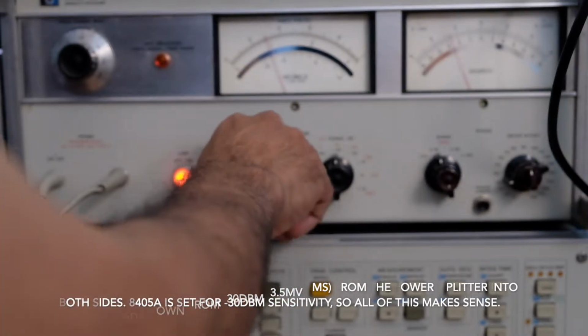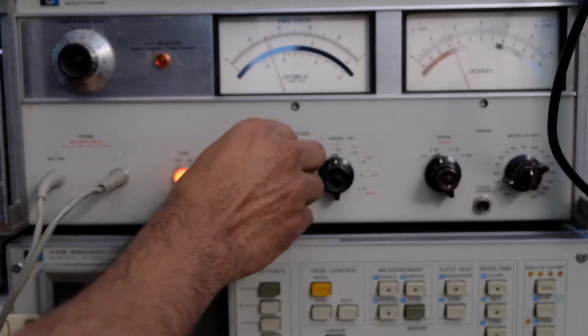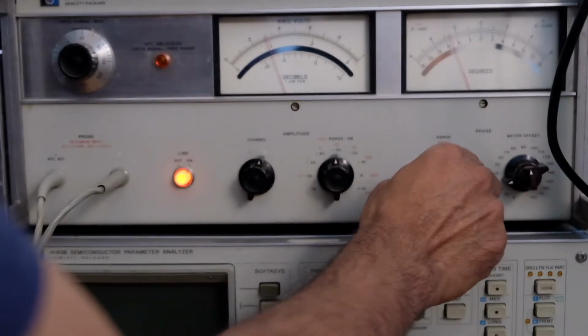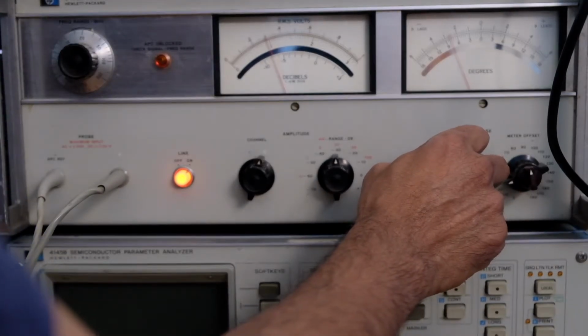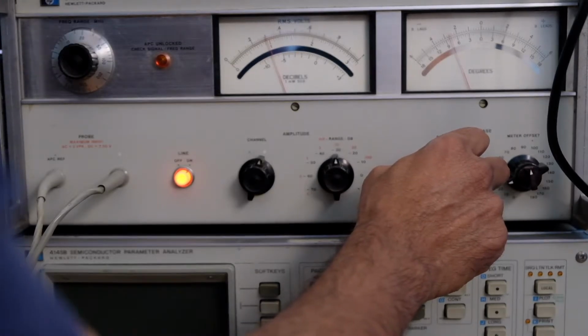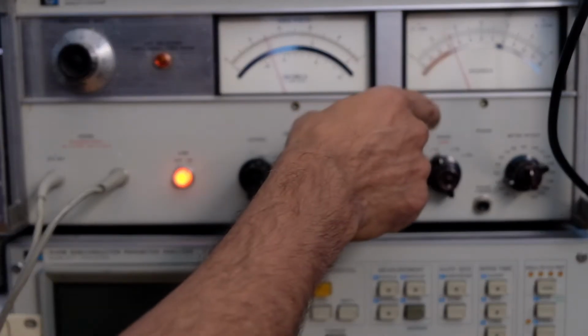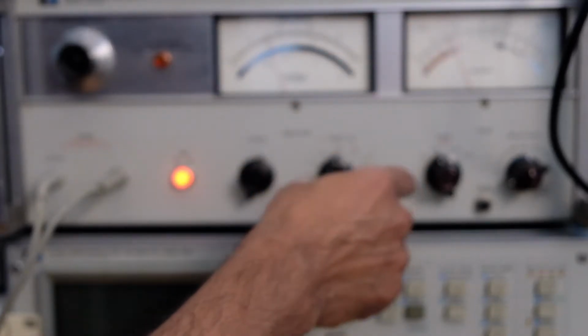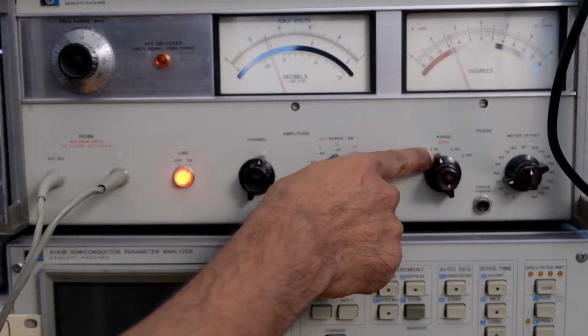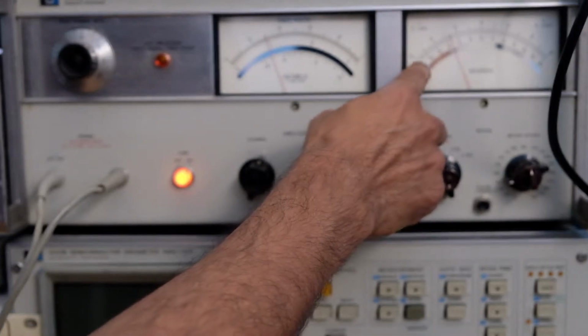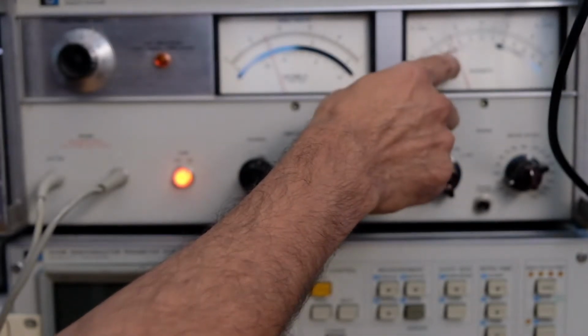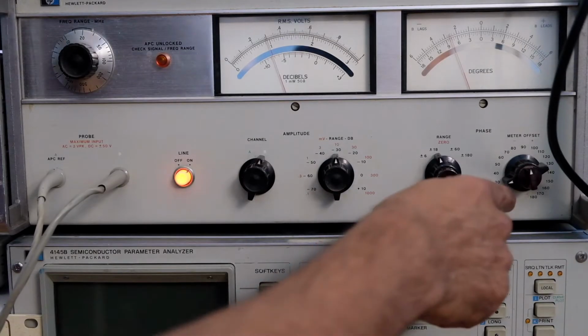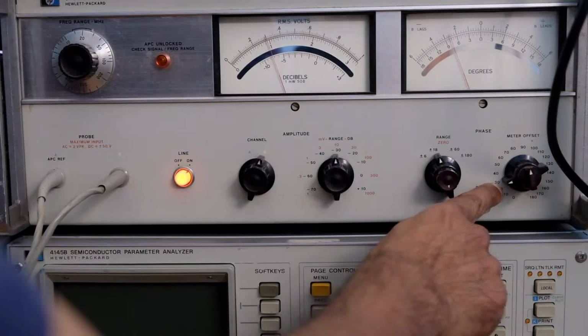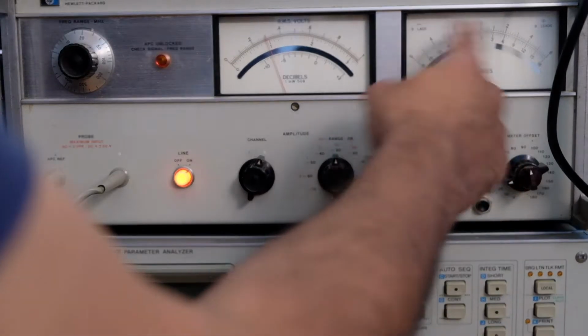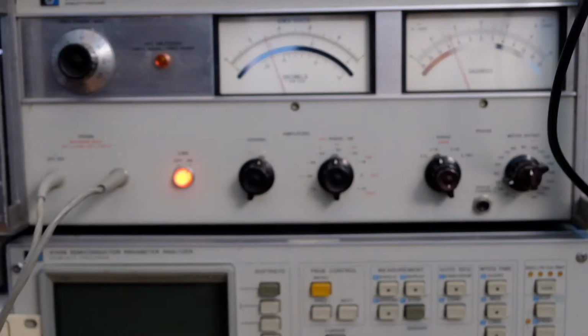So I'm mostly interested in the phase. The amplitude is not going to drop very much for this type of cable. So the phase is now measured at minus 37.5 degrees, I would say. It's exactly halfway between 6 and 9 on the 18 degree scale, which is a lower scale. So that is 7.5 degrees on this one, plus the additional 30 degrees, so 37.5 degrees is the phase difference between channel A and channel B.